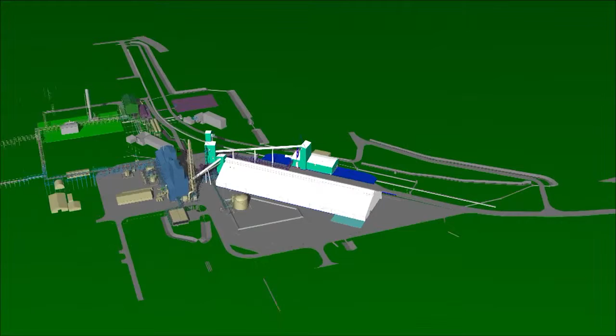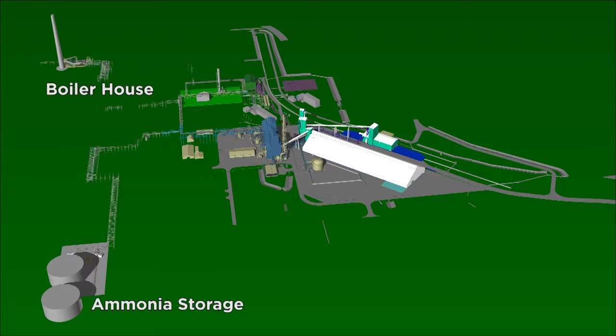While most of the construction activities will be taking place in the area seen here, there will also be construction in the ammonia storage and boiler house areas of the facility. High-pressure ammonia pumps will be installed near the existing ammonia storage tanks to transfer anhydrous ammonia to the new urea unit. Up at the boiler house, the existing Riley boilers would not be able to produce enough steam to meet the demands of the facility and the new urea unit. So a new package-style boiler will be installed to increase the steam capacity for the entire facility by 200,000 pounds per hour.